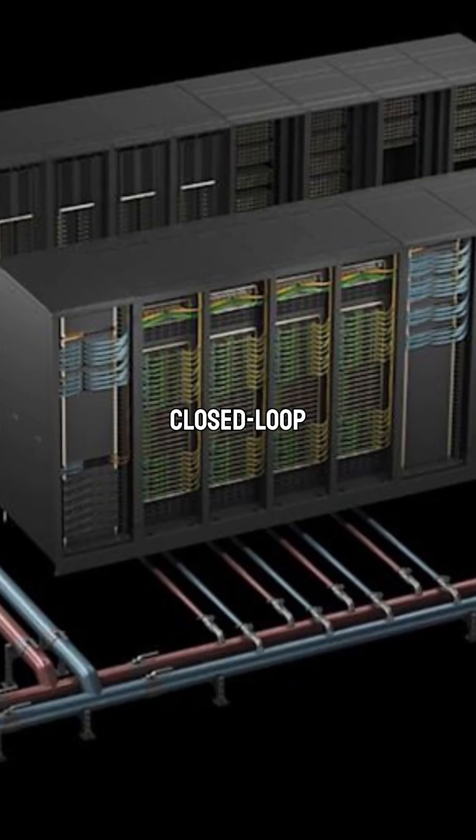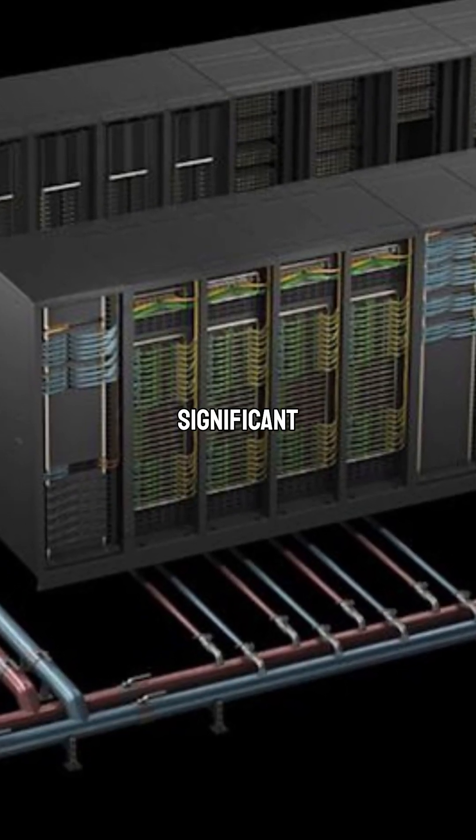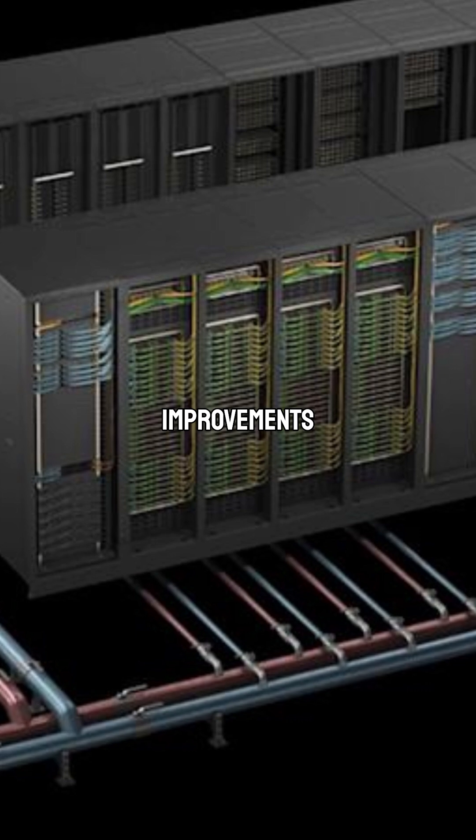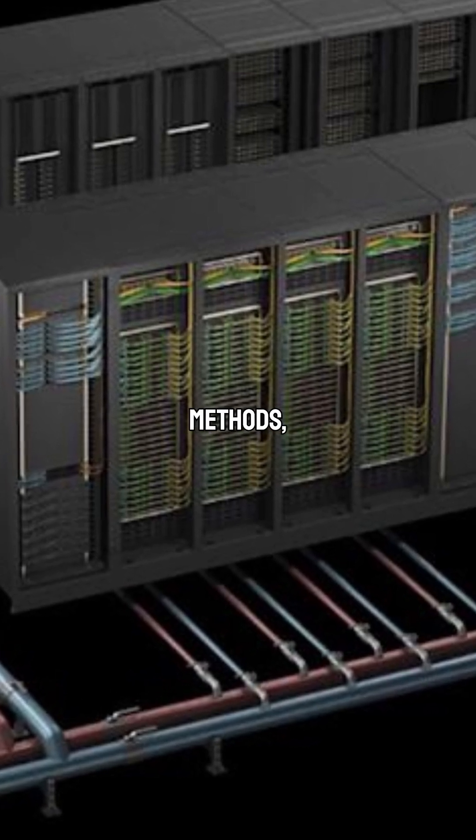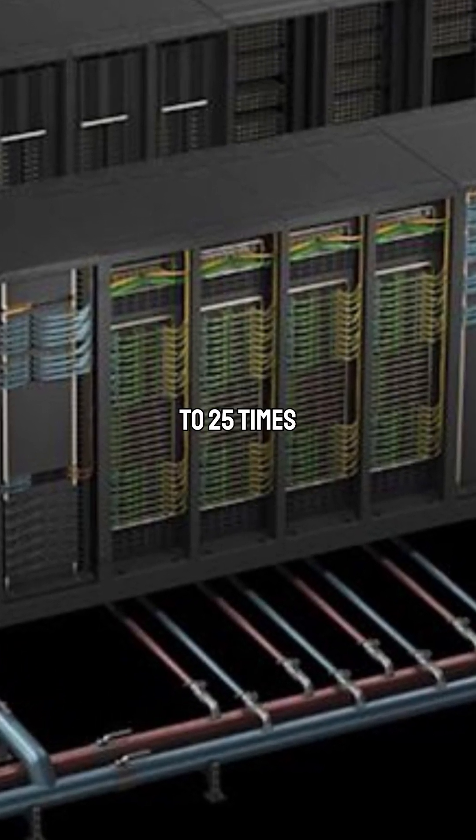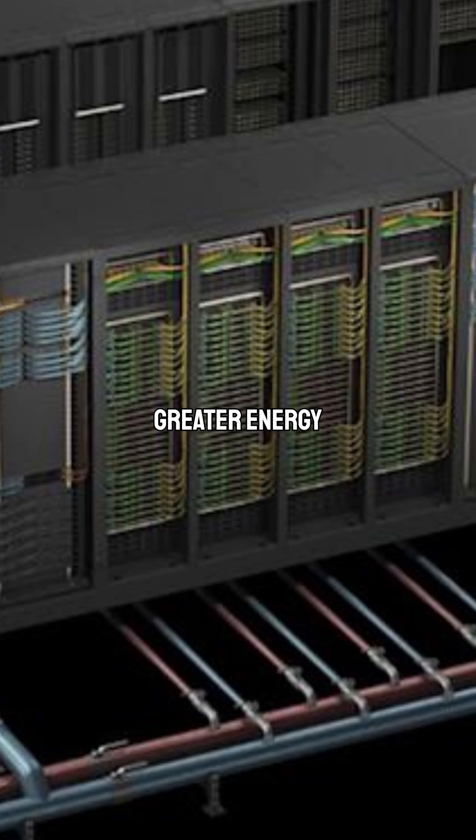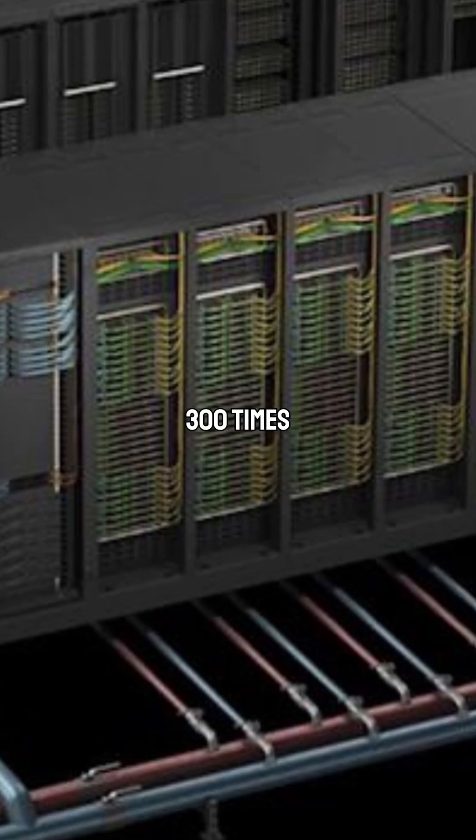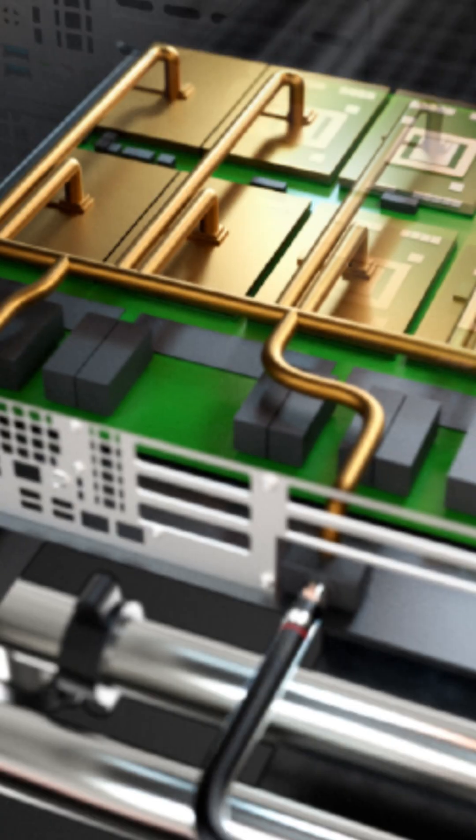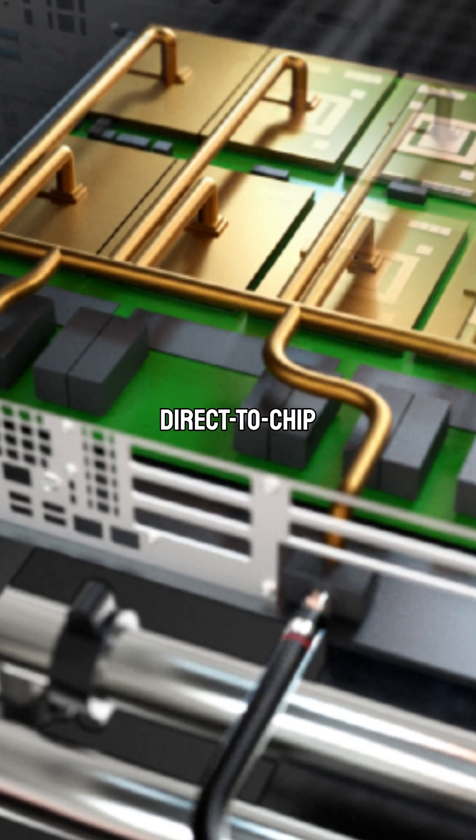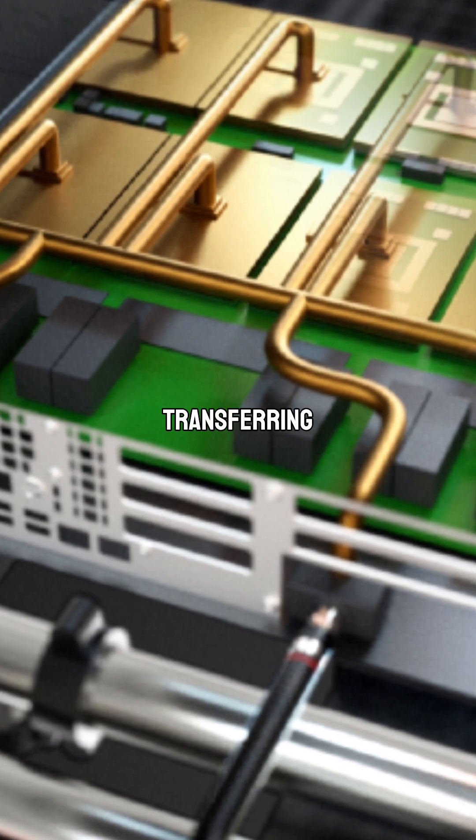This closed-loop cooling technology offers significant improvements over traditional air cooling methods, achieving up to 25 times greater energy efficiency and 300 times better water efficiency. The direct-to-chip cooling approach involves transferring heat directly from the processors to a liquid coolant.